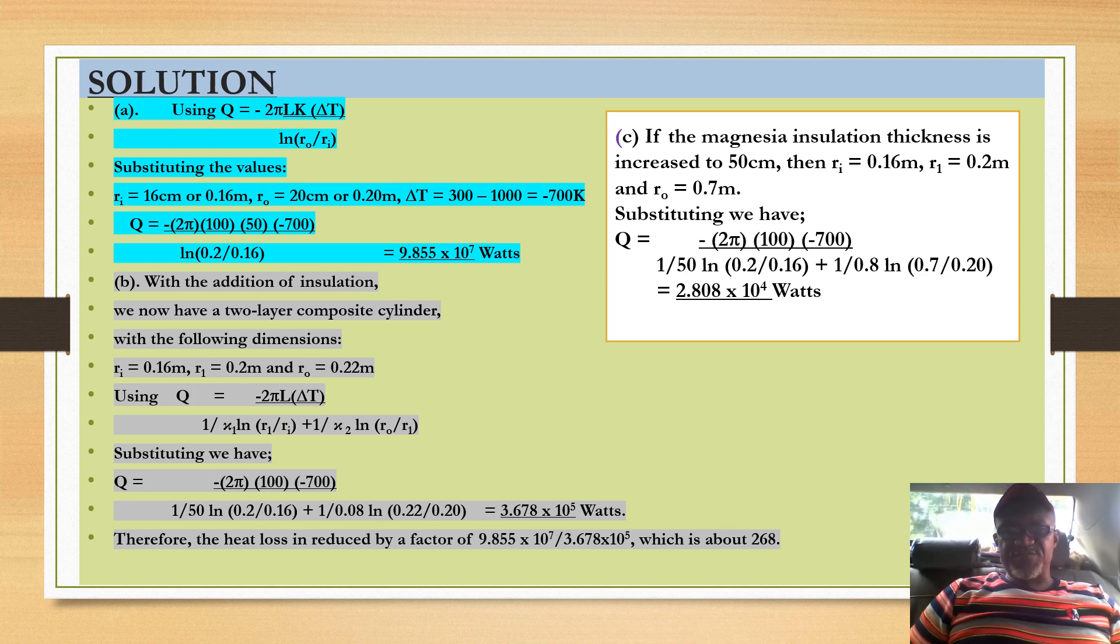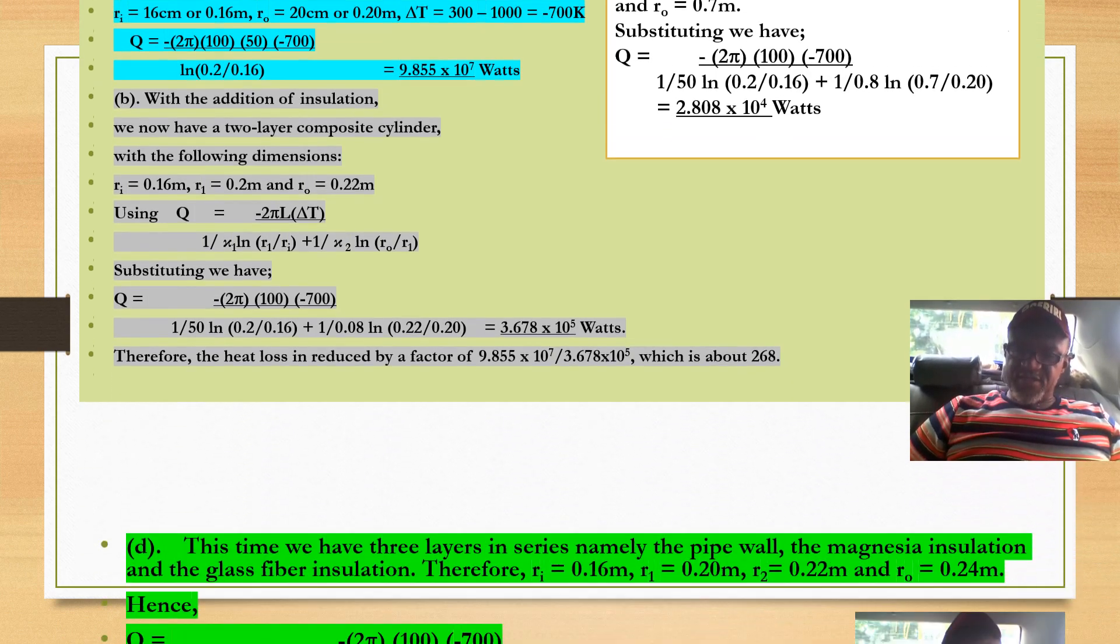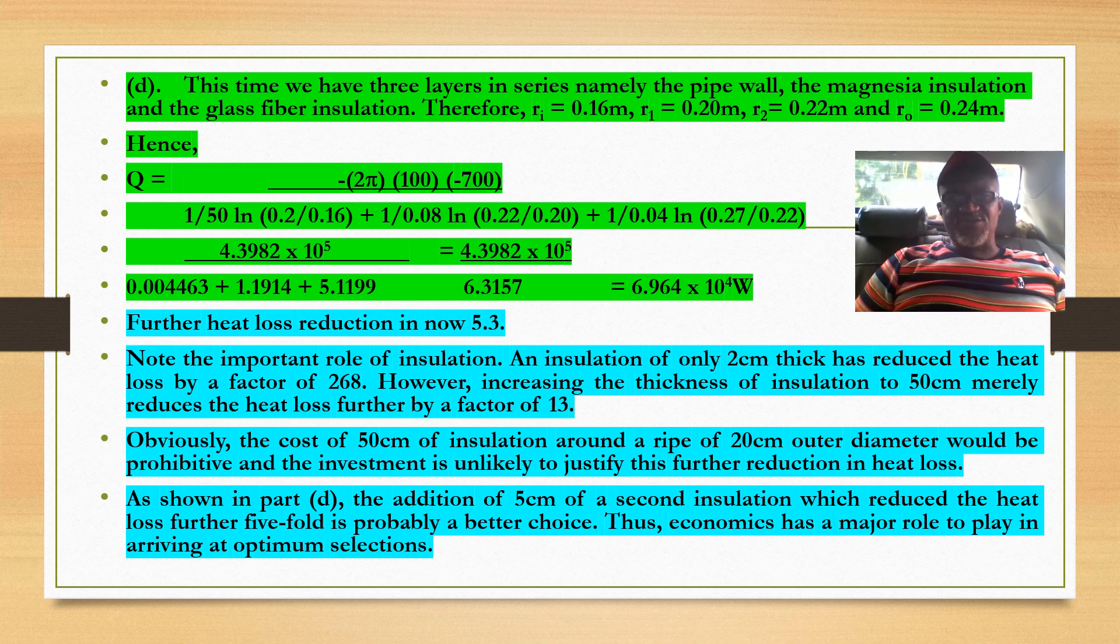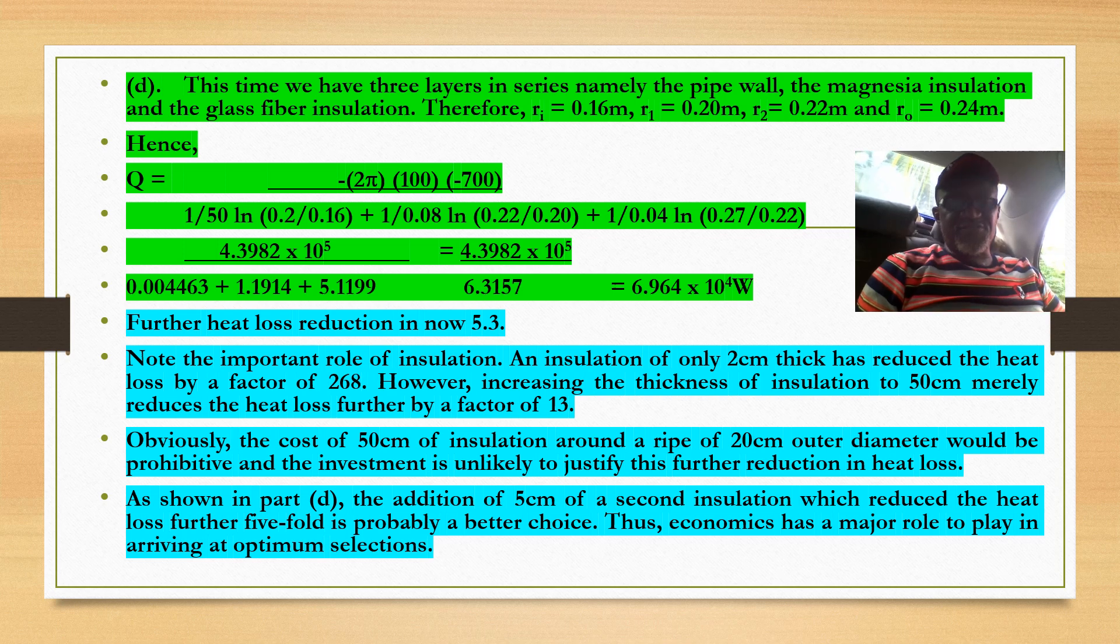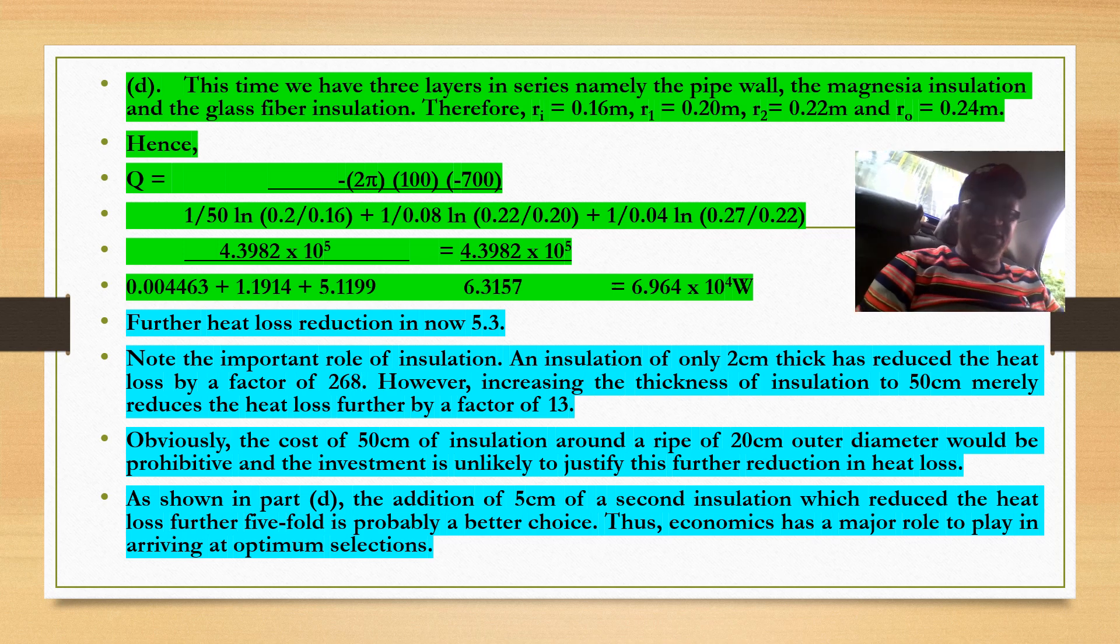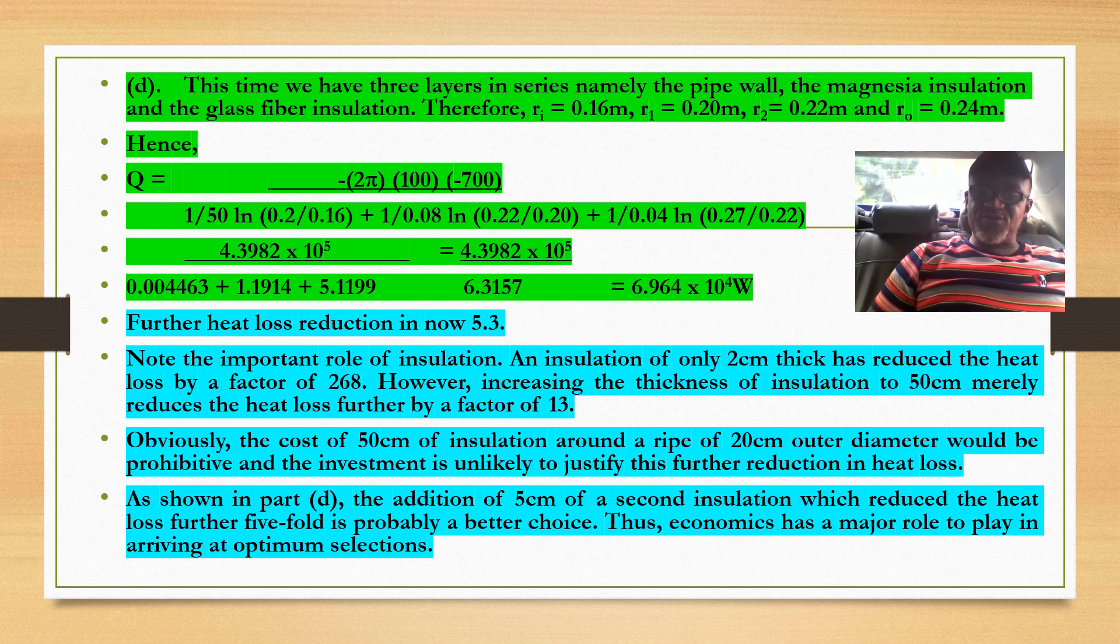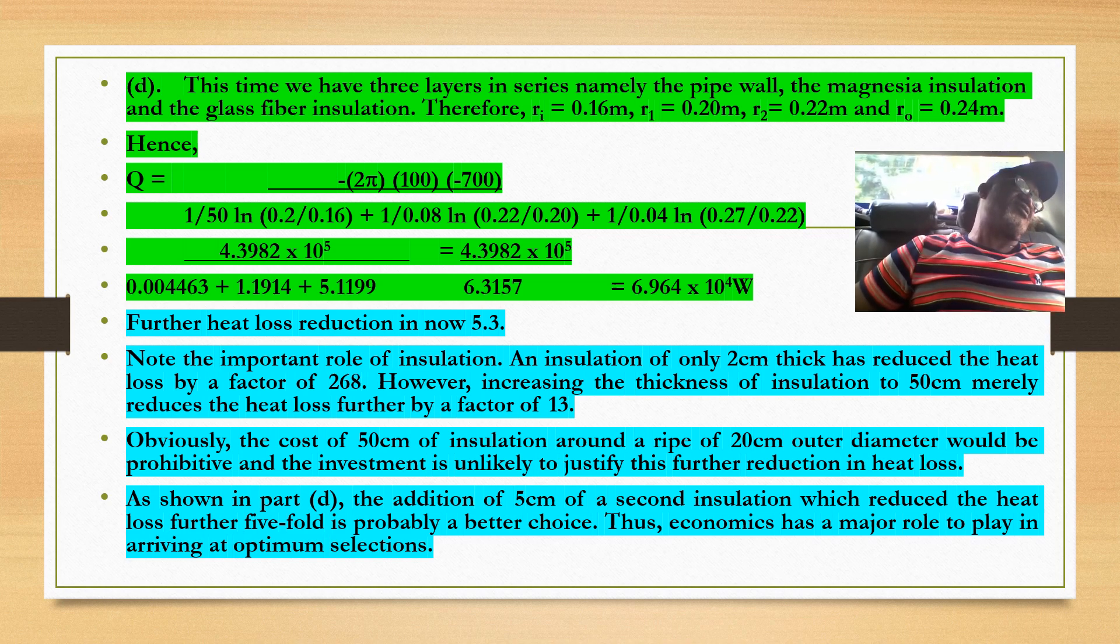When we solve this, you will see that in part (b), heat loss is reduced when we put the first insulation. In part (c), we increase the thickness and observe further heat loss reduction. In part (d), instead of increasing thickness, we add another insulation layer. You see that adding another 2cm insulation is far better. This means 50cm construction would be very exorbitant. It's better to have 2cm coating of a second material than 50cm coating of the first. This is the essence of these calculations - you must calculate before construction, otherwise you waste money assembling materials only to find they don't work as expected.